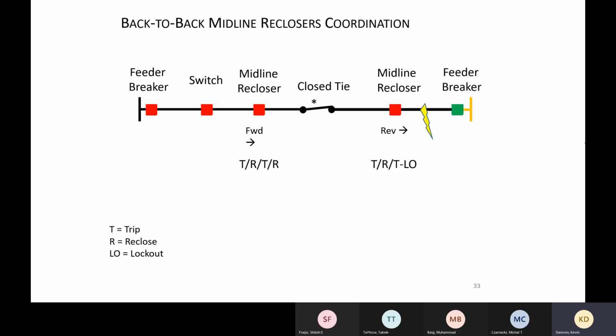So if we're in this configuration and we have a fault here, then both devices are going to trip. In most instances, these two devices are set either really close to one another or sometimes almost identical. So for a fault here, both of them are going to see it and trip, and then they'll both reclose. If the fault's permanent, then they're both going to trip again. The difference here is this one trips and locks out at that point. So I get one reclose trying to restore this section. But this recloser goes through another reclose to pick up everything except for this breaker. So at this point, I've locked out this breaker. Now I'm picking everything back up to this midline recloser, and I've isolated the fault to this bus section.